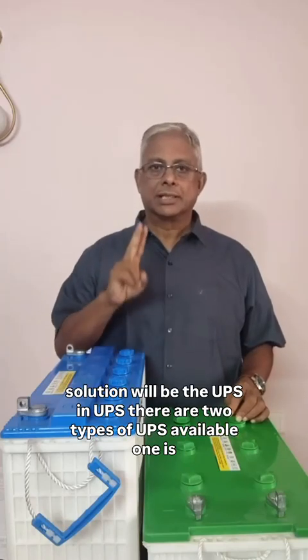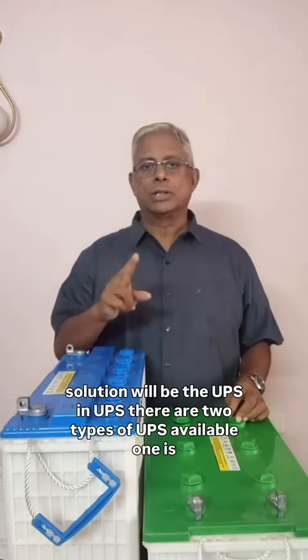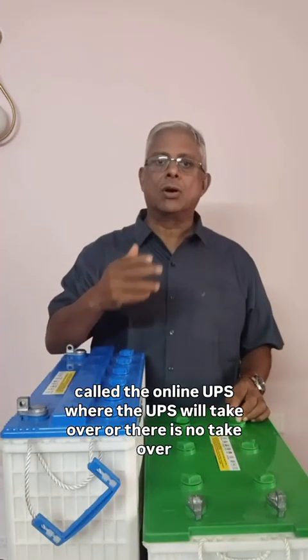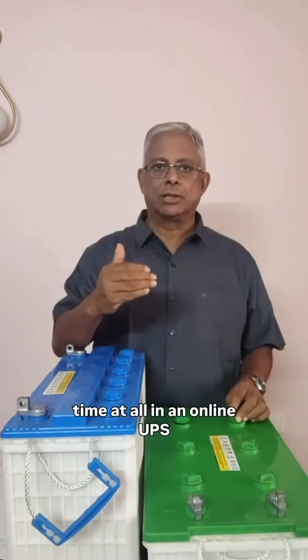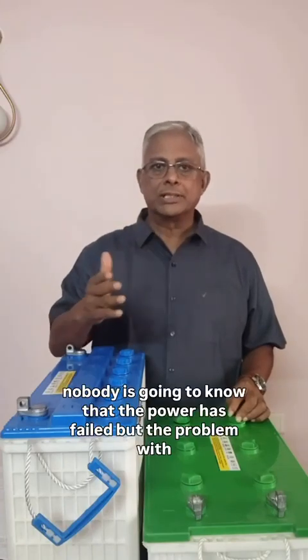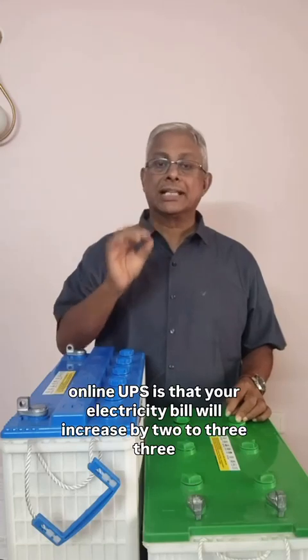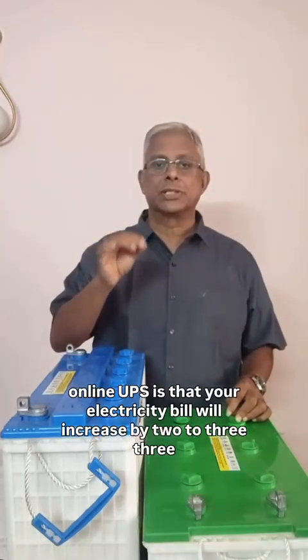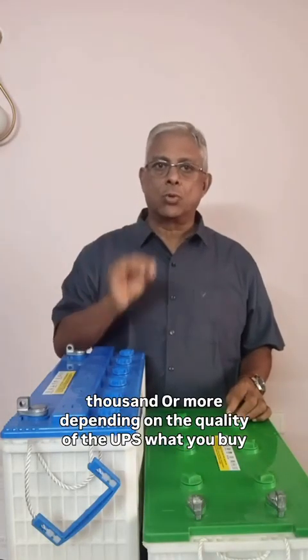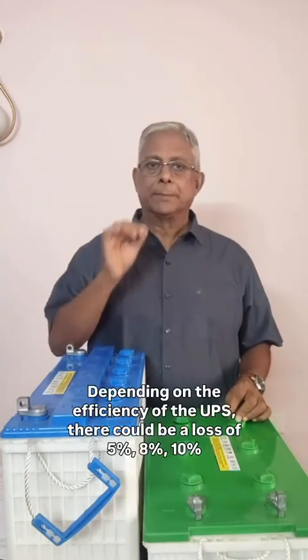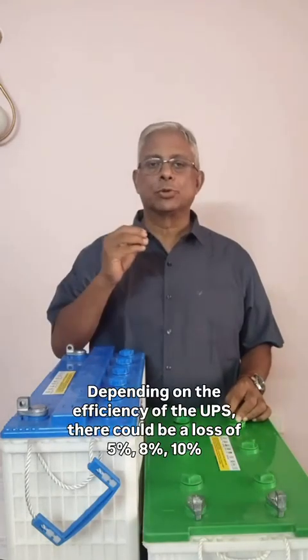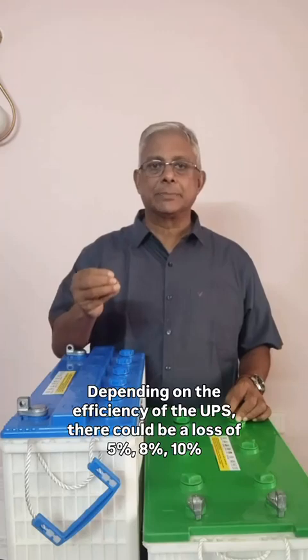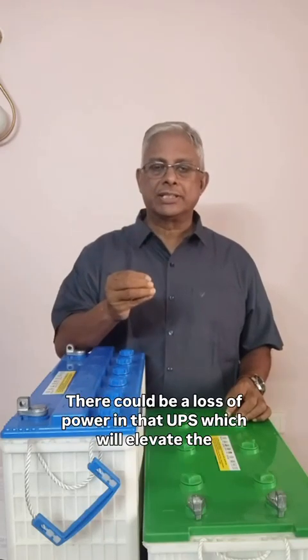There are two types of UPS available. One is called the online UPS, where there is no takeover time at all. In an online UPS, nobody will know that the power has failed. But the problem is that your electricity bill will increase by 2,000 to 3,000 or more, depending on the quality and efficiency of the UPS. There could be a loss of 5%, 8%, 10% of power in that UPS, which will elevate the electricity bill.